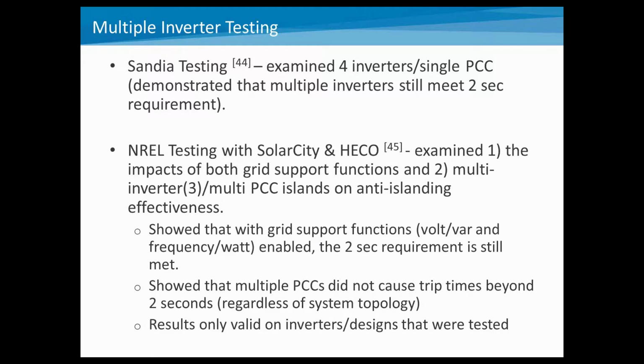But really the results showed that with grid support functions enabled, so volt var control and frequency watt enabled, the 2-second requirement was still able to be met. It also showed that multiple PCCs did not cause trip times beyond 2 seconds, regardless of system topology. So again, this was scattering multiple inverters at multiple points of common coupling, and then doing the same type of unintentional islanding test on that much larger system.